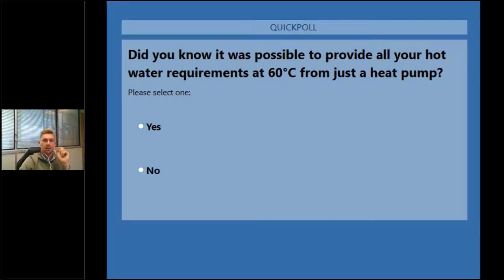Did you know? And also, the other thing to mention at this point actually is when you're working in hot water mode, you'd be looking at your high temperature SCOP, and your high temperature SCOP will be published on the back of any bit of literature for an air source heat pump. That's a heat pump return of 55 degrees centigrade, because obviously as the cold comes in, tank fluctuates in temperature. You're looking at efficiencies of anything between 300 and 320% for that schematic we just looked at, which I think is a pretty impressive number for domestic hot water produced from an air source heat pump at over 60 degrees. Okay, cool. Cancel the poll. Let's go on to the next section.